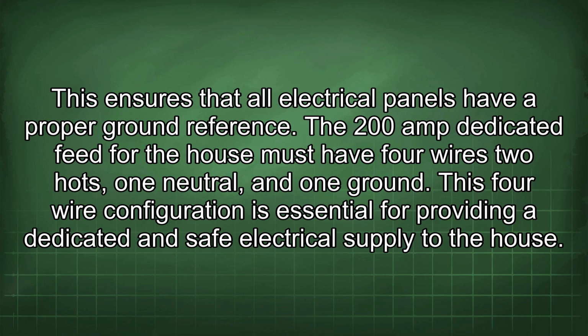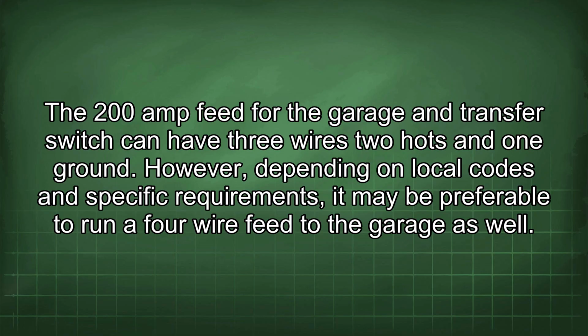The 200 amp dedicated feed for the house must have 4 wires: 2 hots, 1 neutral, and 1 ground. This 4-wire configuration is essential for providing a dedicated and safe electrical supply to the house. The 200 amp feed for the garage and transfer switch can have 3 wires: 2 hots and 1 ground.